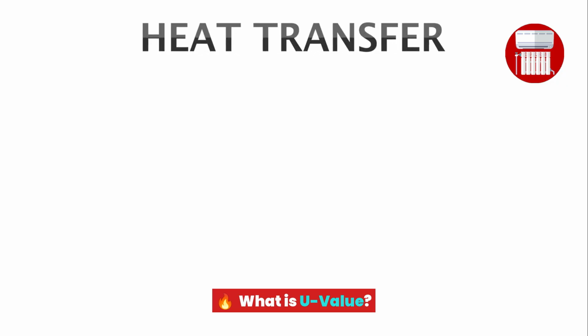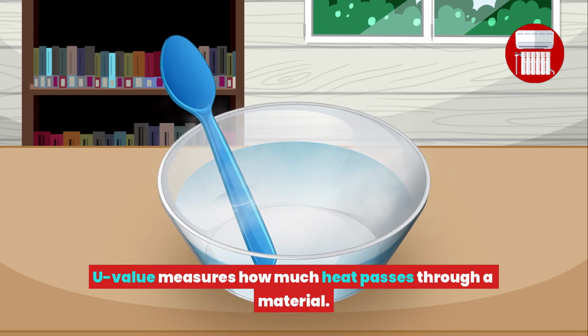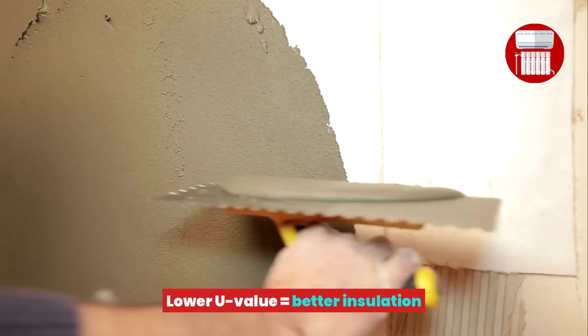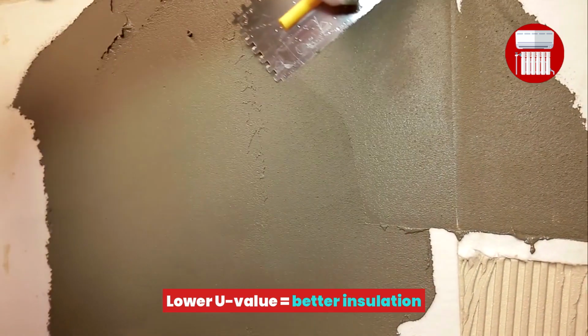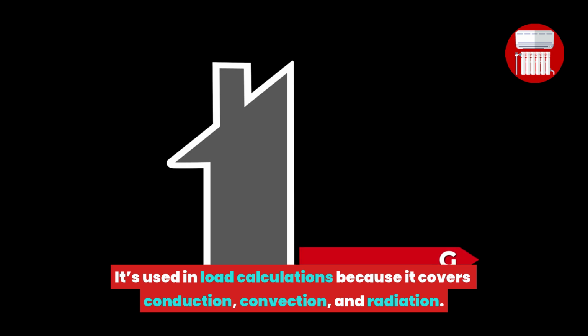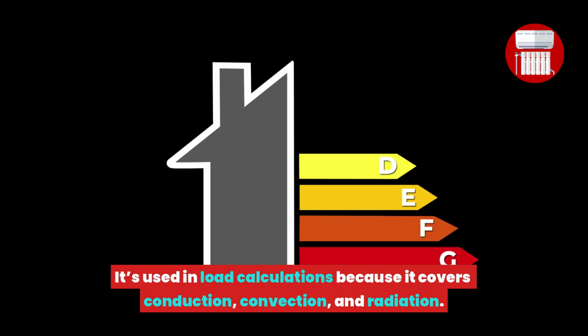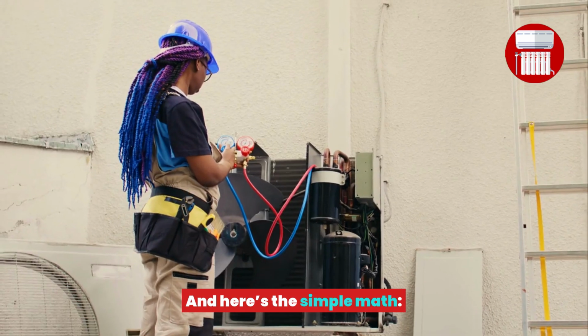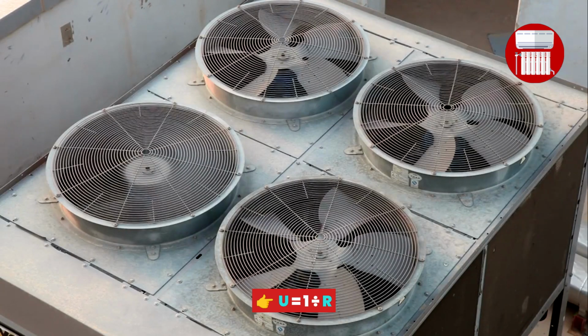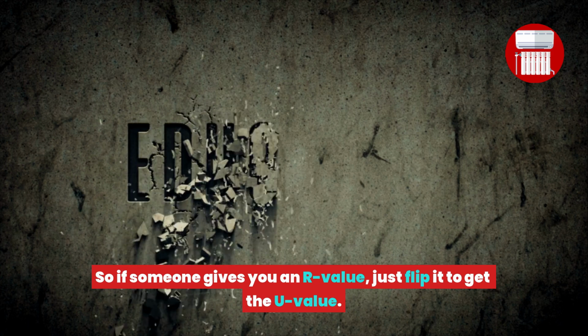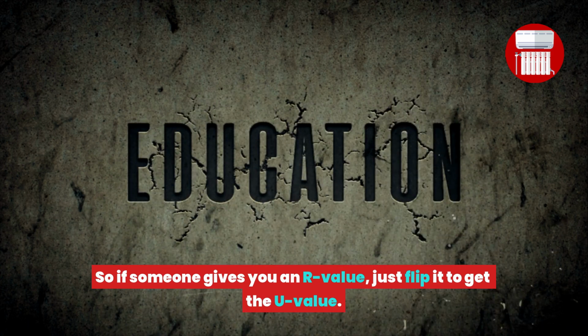What is U value? U value measures how much heat passes through a material. Lower U value equals better insulation. It's used in load calculations because it covers conduction, convection, and radiation. And here's the simple math. U = 1/R, R = 1/U. So, if someone gives you an R value, just flip it to get the U value.